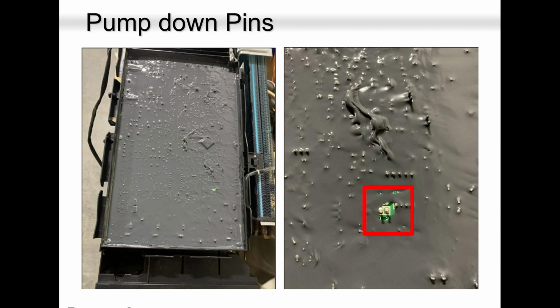It's fully insulated to protect against water and snow. That doesn't mean you pour a whole bucket of water to test it. No, please don't do that. But in the same PCB, there is a spot here where I highlighted. It's not insulated. The reason being, it's there for you to short it if you need to pump down the system.